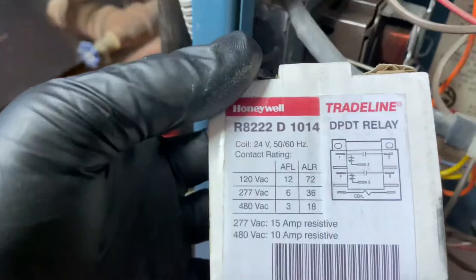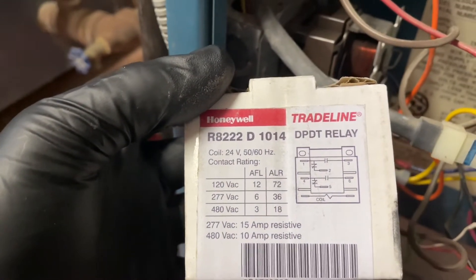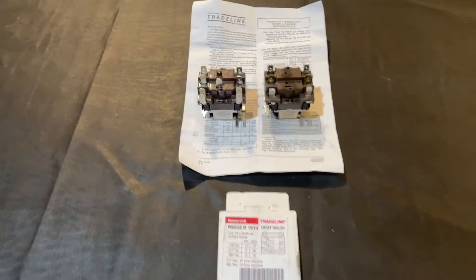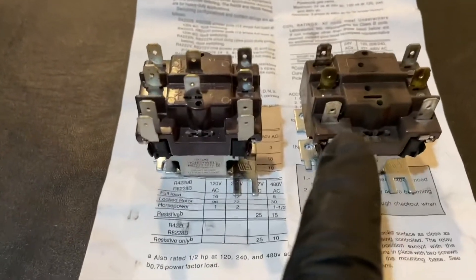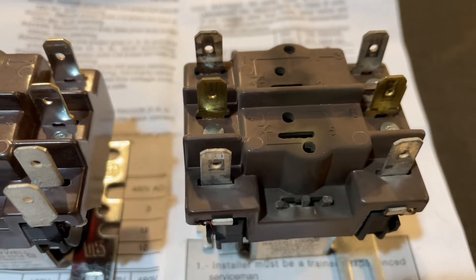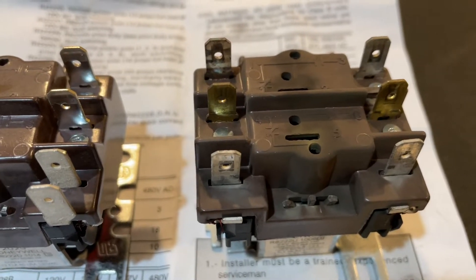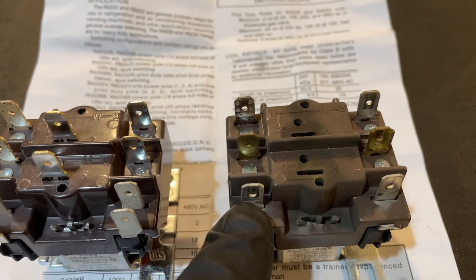I got the replacement right here, the Honeywell R8222D-1014. I want to make a little modification to it — I'll show you that in a minute. So here are the two relays, these coil relays, side by side. The one on the right, as you can see, it's got some discoloration on it. This is the one we took out of the fan center relay, that Honeywell component inside the boiler. It has the transformer, and it has the mounting bracket for the relay, and the one on the left is my new relay.